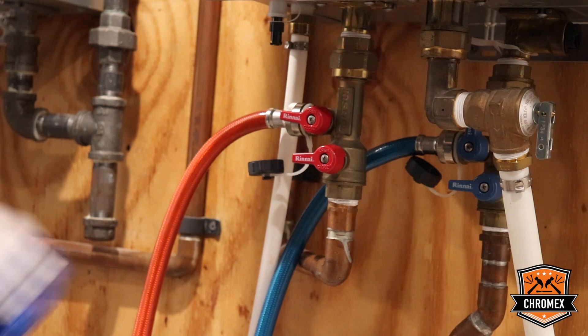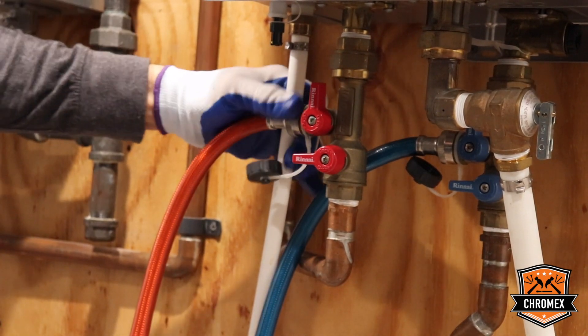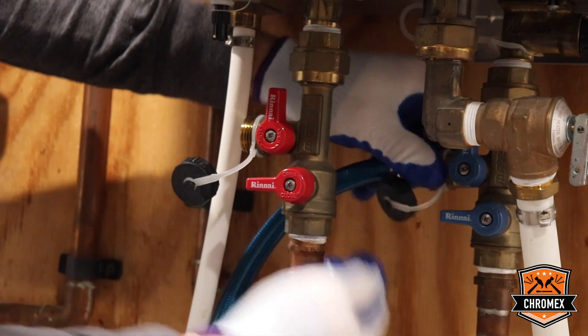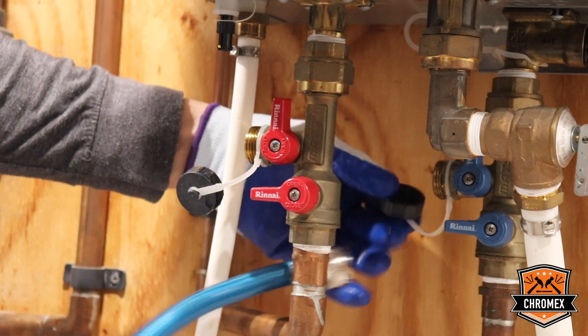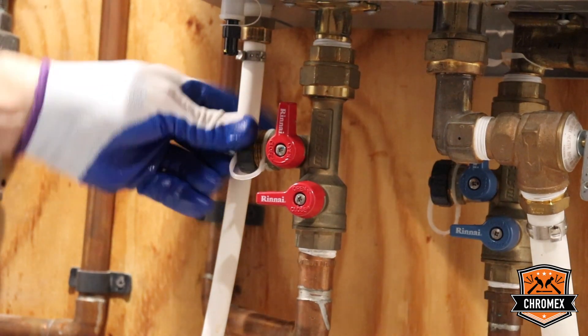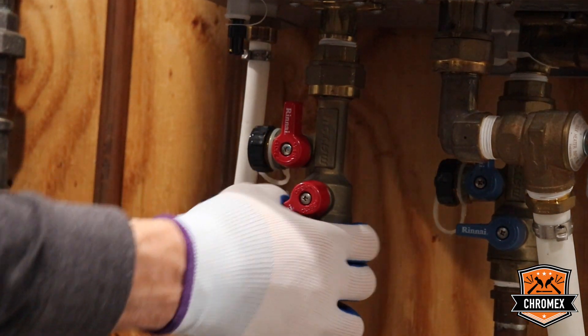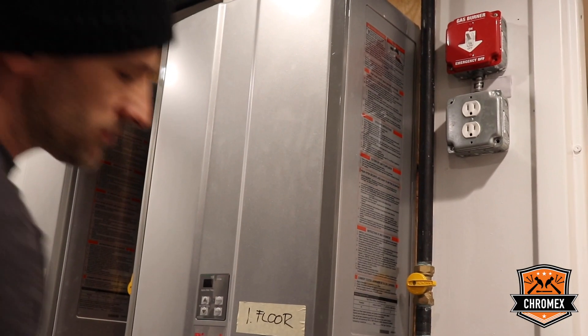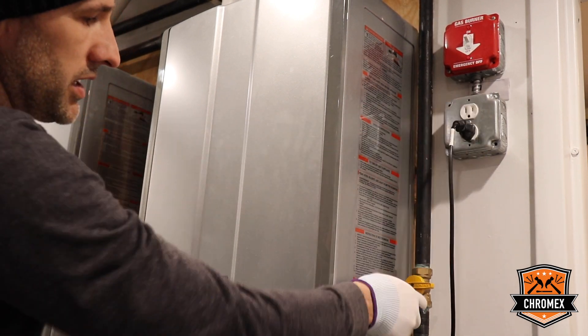After we flush through the system, we have to close the hot water service valve and remove all the pipes — closing the hot water side and the cold water side, and replacing the caps. Then turn on the isolation valve. To restart the system, we have to reconnect the electric line and open the gas valve.